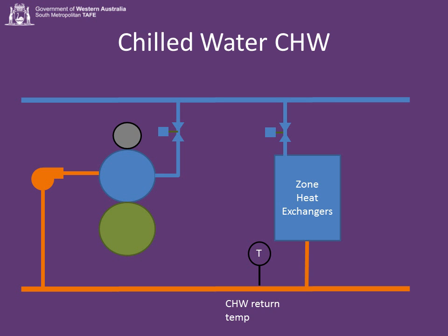The chilled water goes out on the chilled water header. That's at the top there, that's the blue for cold. It goes off to the zone heat exchangers, and then it comes back from the zones, and of course it's warmer now. We typically control to chill water return temperature. So we try and maintain the chill water return temperature to, not too high. Sometimes we control to chill water supply temperature, and we'll control that to about 5 or 6 degrees Celsius. We have a chill water pump that pumps the water through the chiller.